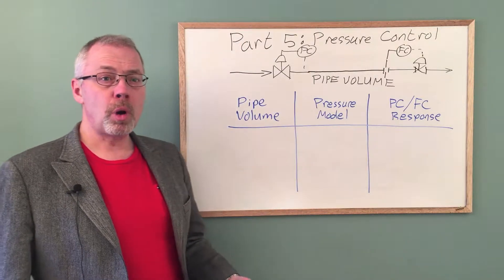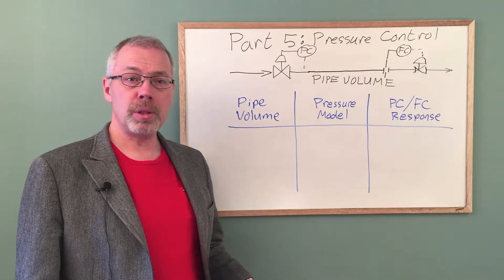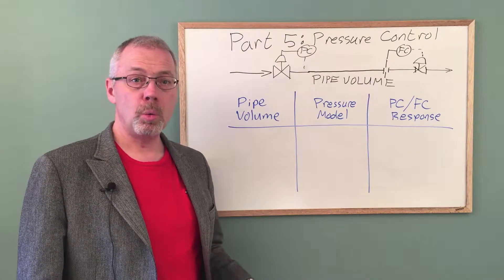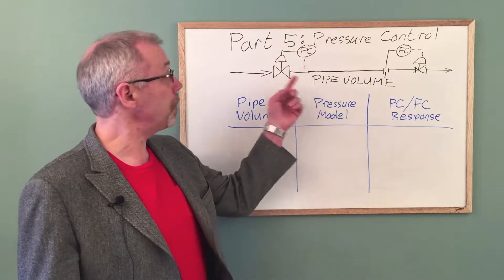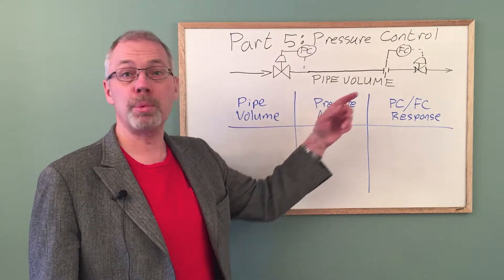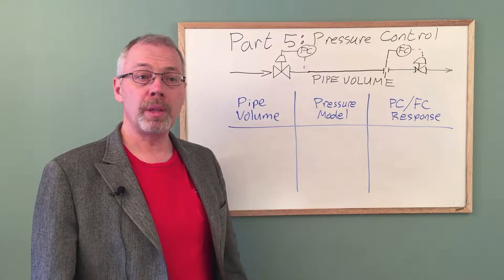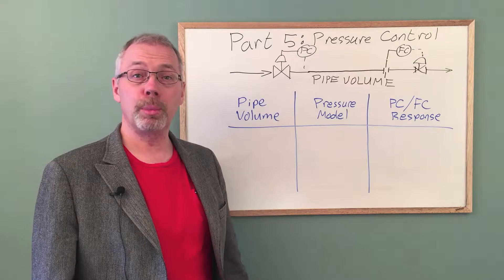Pressure control is commonly used on utility supply systems to ensure reliable performance of a flow controller. We will look at an example where fuel gas pressure is controlled on the upstream side of a flow controller. One example of this is the firing train for a boiler.